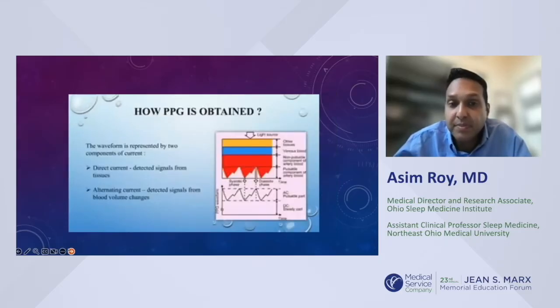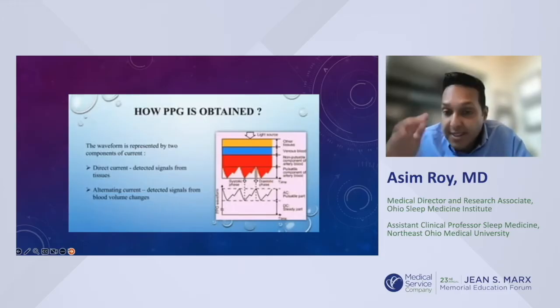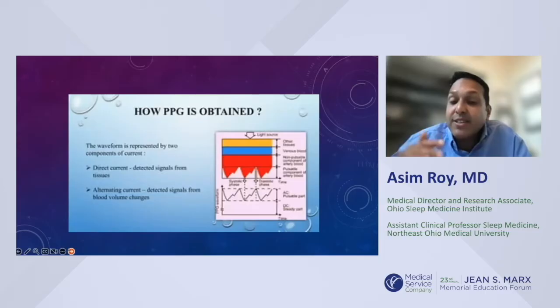There's a direct current that is detecting the signals from the tissue directly, and an alternating current that's detecting signals from blood volume changes. So the change in blood volume is determining the signal. When it's pulsatile, like your arteries sending a pulse, those variations, those changes are what's being monitored by the PPG, and these small changes are what create a signal to determine different biometric parameters.